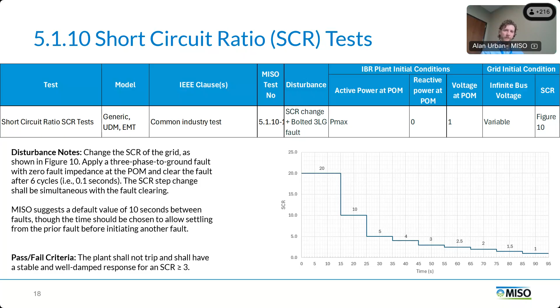And then the last test here, just for EMT models, is a phase angle change test. Again, just making sure the plants don't trip, and that they're stable and well damped. So also making sure that there's no momentary cessation. We did also consider for just the EMT models a transient overvoltage test, but I don't believe 2800 touched on the transient overvoltage test, so we opted as well not to touch on that test. So originally it was part of our draft requirements, but we pulled it out before we started circulating it among stakeholders.